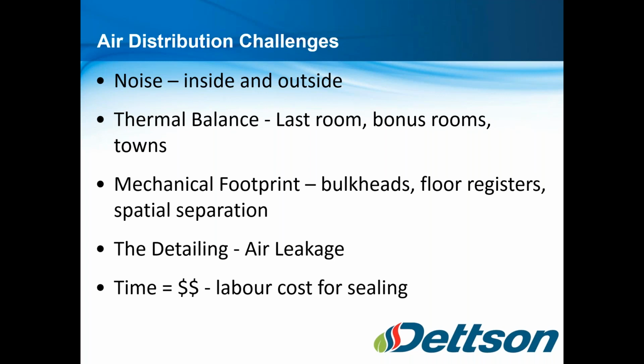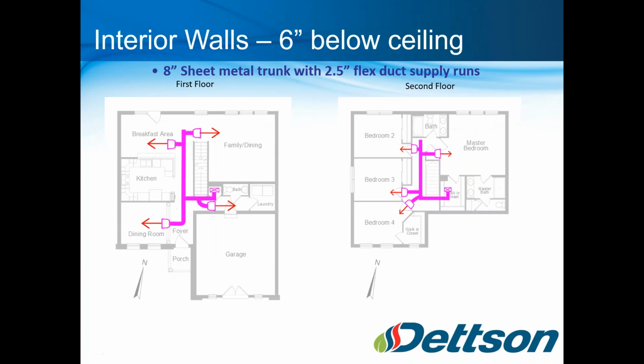And all of that time it takes for air leakage. So our system will absolutely work with a traditional duct system. Just get it under 10% leakage. That does take extra contractor time and detailing and labor, which equals money, to get that air leakage down in the ducts. So we wanted to look at that to help potentially, and this is where the show me the money part is, so help offset the cost of getting a better, modulating system, and offset the cost of doing that. So labor, detailing, consistency in installs, as well as just overall better systems. So therefore, cutting down the warranty callbacks. So our system, we install it 6 inches from the ceiling.